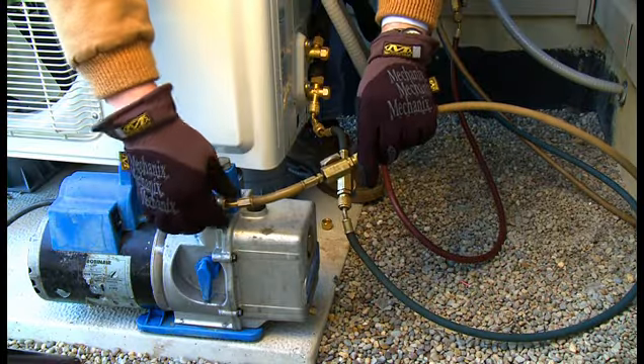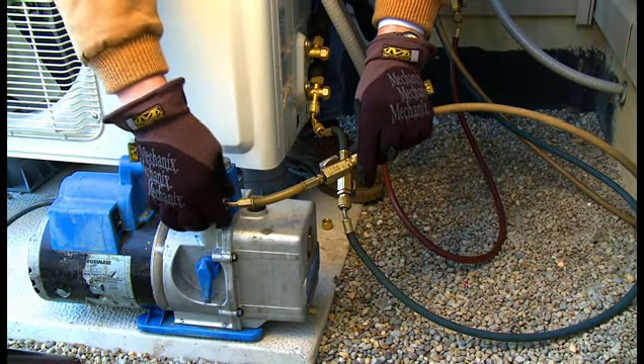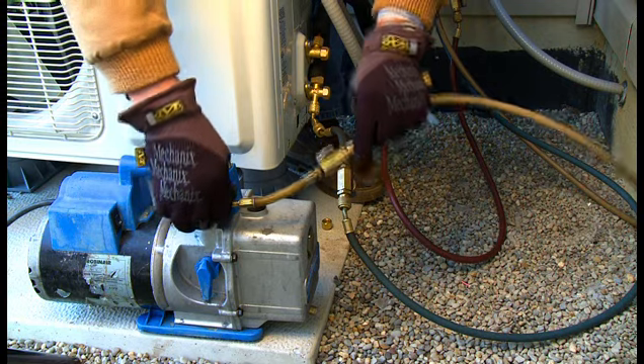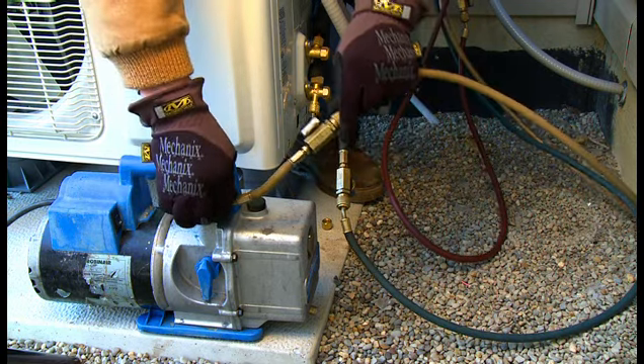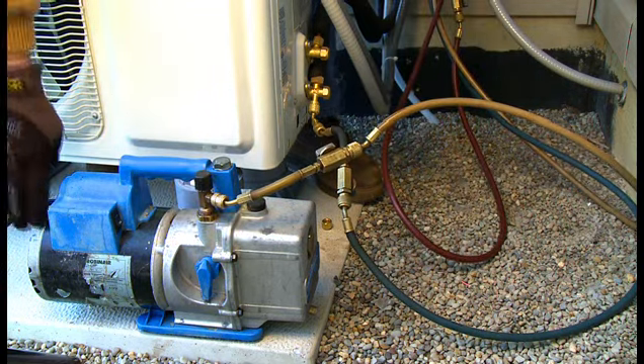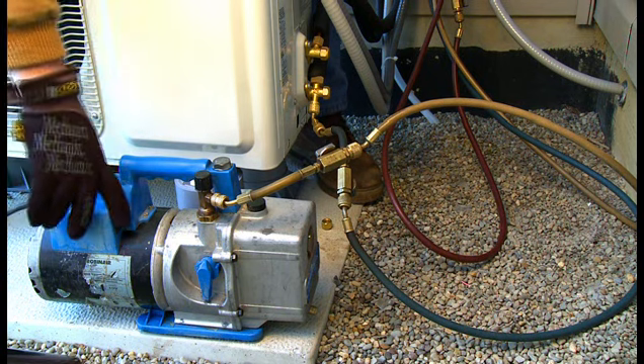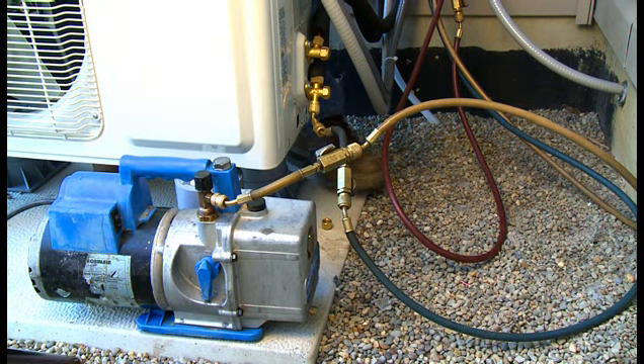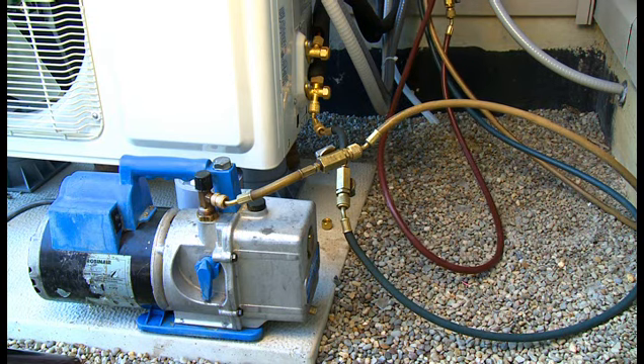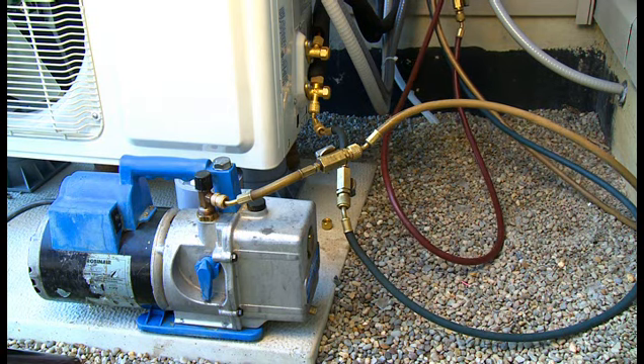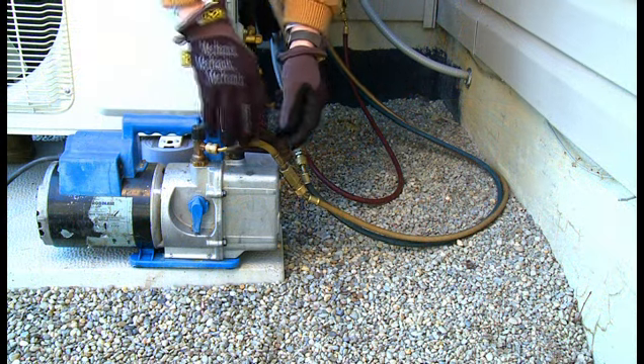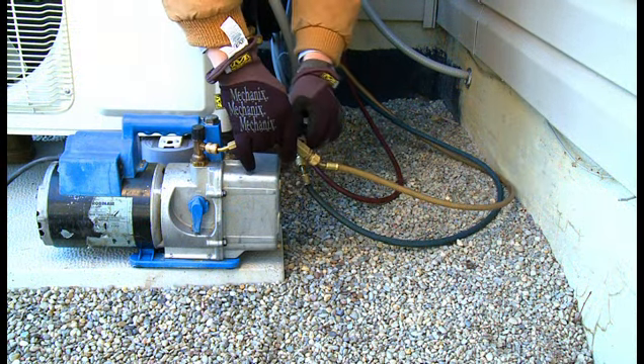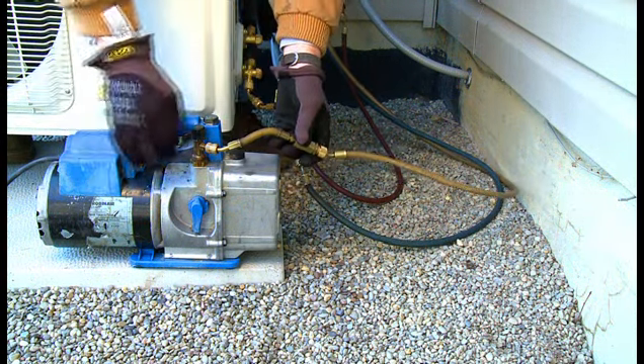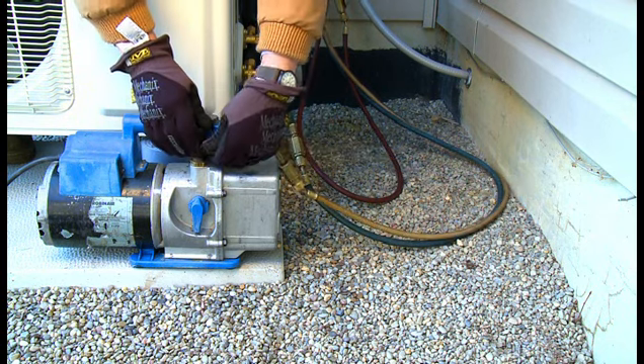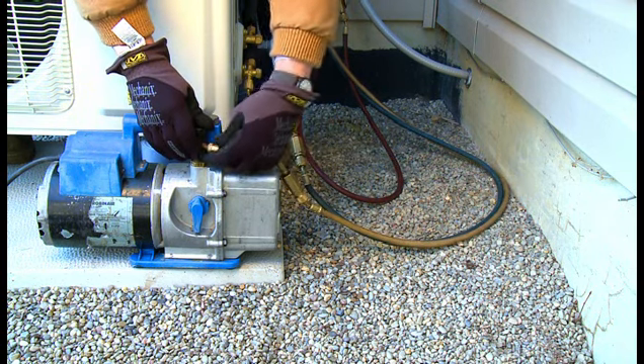We will now use a vacuum pump, vacuum meter, and the pressure control valve to remove air from the system. Connect the pressure control line and valve to the vacuum pump. Turn on the vacuum pump to begin the evacuation of the line sets and the interior unit. Evacuation requires about 15 minutes or more. After the evacuation has been completed, close the pressure control valve. Turn off the pump. From the vacuum pump, disconnect the pressure control line and valve.